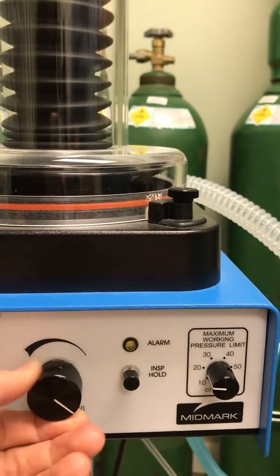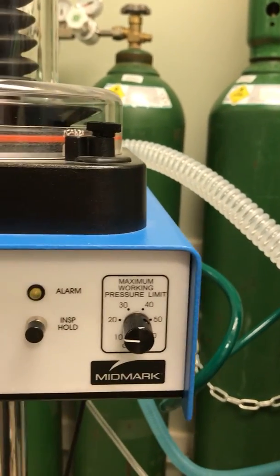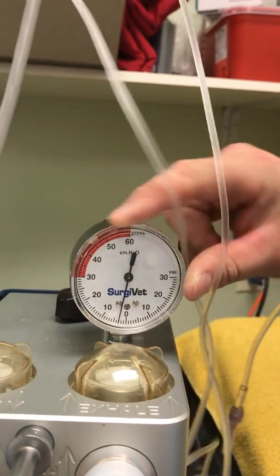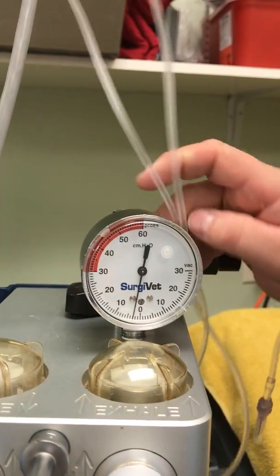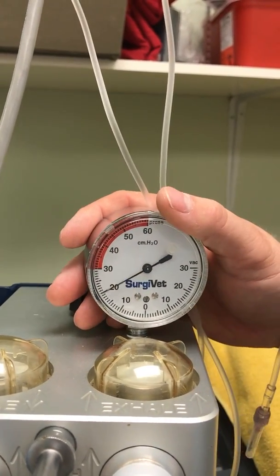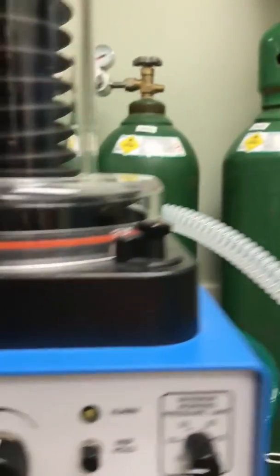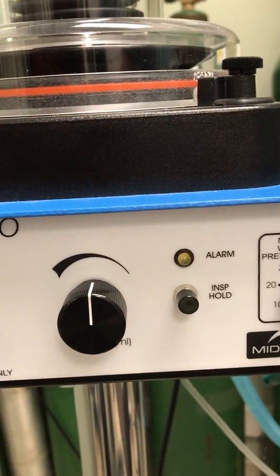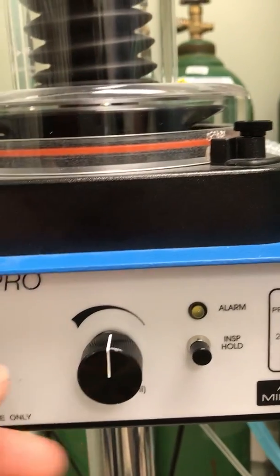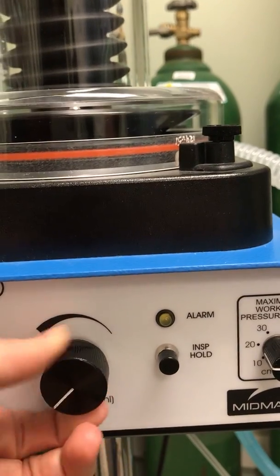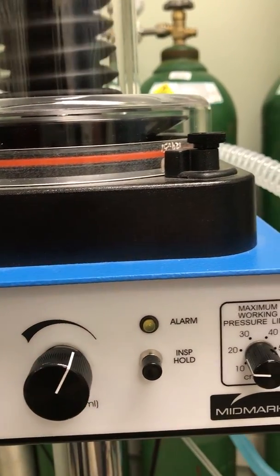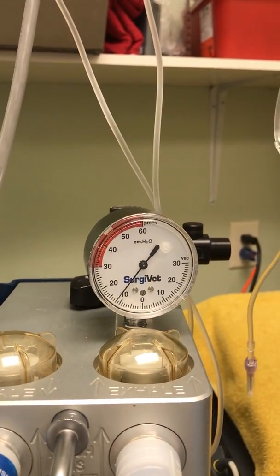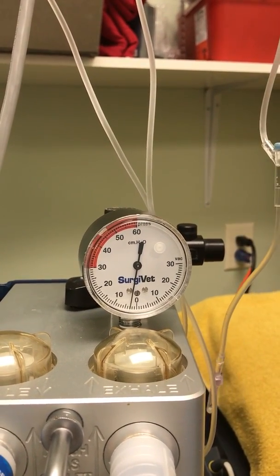I'm going to demonstrate that. Alright, so now here on this pressure gauge we're going over 20, and so there's an alarm sounding that tells you that pressure is going too high. Now remember that this does not stop that pressure from occurring. So if that alarm is occurring, your patient is getting that pressure into their lungs, which can be dangerous. So we want to make sure to correct that immediately.